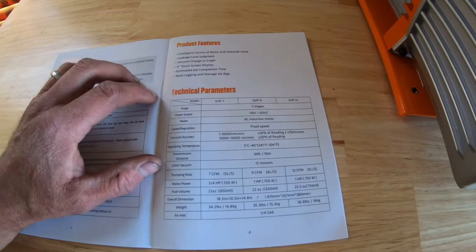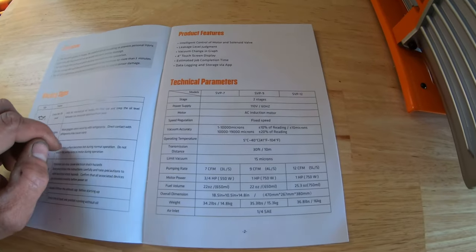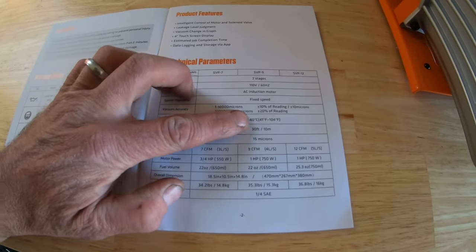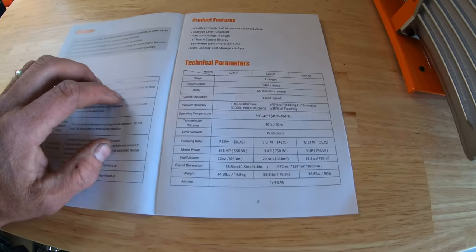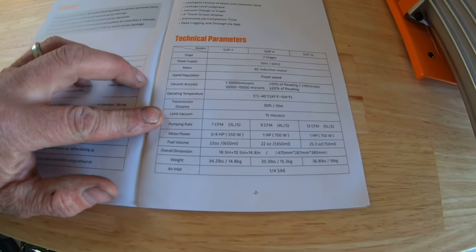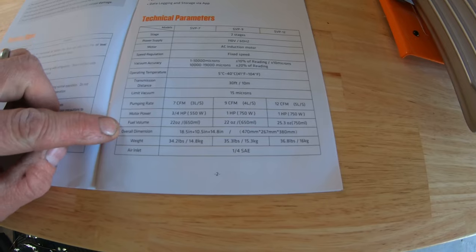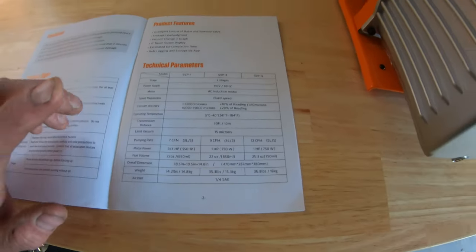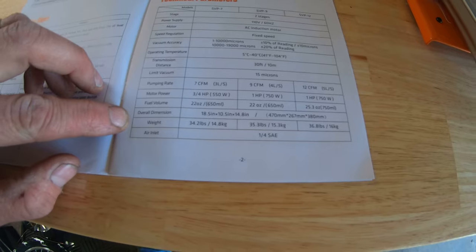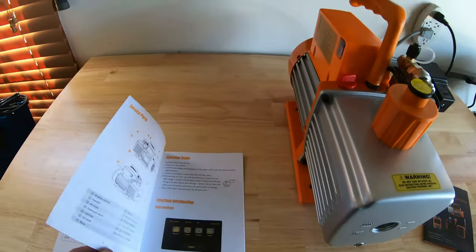The SVP12 is a two-stage pump, 110 volts, 60 hertz, with an AC induction motor — fixed speed. Vacuum accuracy is 1 to 10,000 microns. Operation temperature: 41 to 104 degrees. Transmission distance: 30 feet. Vacuum limit: 15 microns. Pumping rate: 12 CFM. One-horsepower motor. Fuel volume: 25.3 ounces — that's how much oil it takes. Overall dimensions: 18.5 by 10.5 by 14.8 inches. Weight: 36.8 pounds. Air inlet is a quarter-inch SAE.